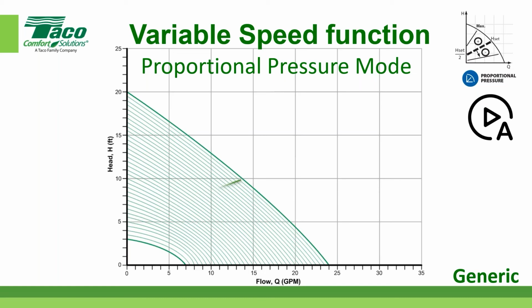So let's jump into this. Notice one thing too, generally speaking again, if I started here at 10 foot ahead at maximum speed, and the direction or the pitch or the angle that this thing came down got me down to the point of 5 feet ahead, 5 is 50% of 10, so this would be a 50% proportional pitch. Okay, and that's something that the manufacturer of the circulator, like Taco or Grundfos or anybody else, would preset within their algorithm of their pump, or the brain within the pump.